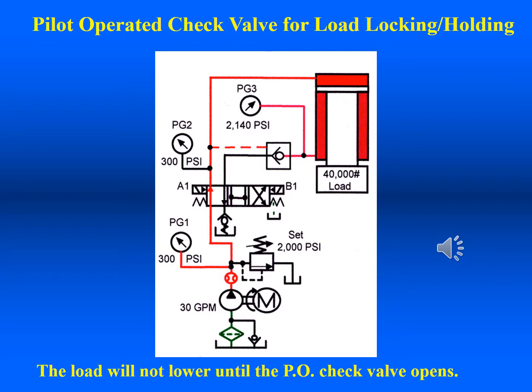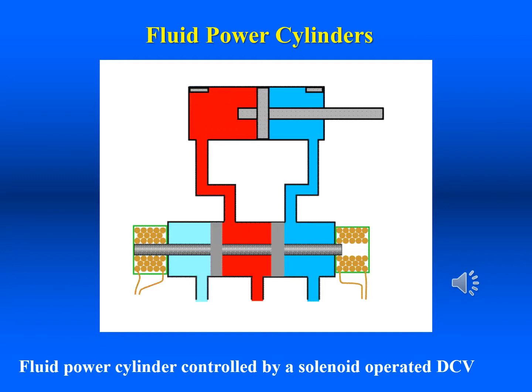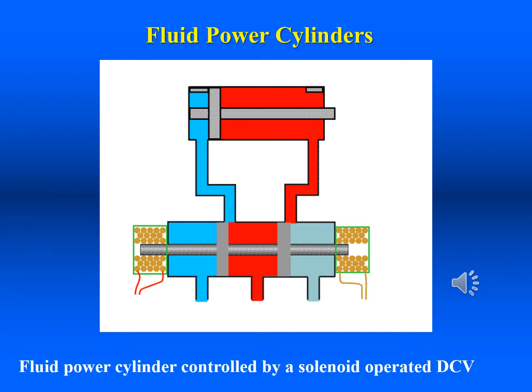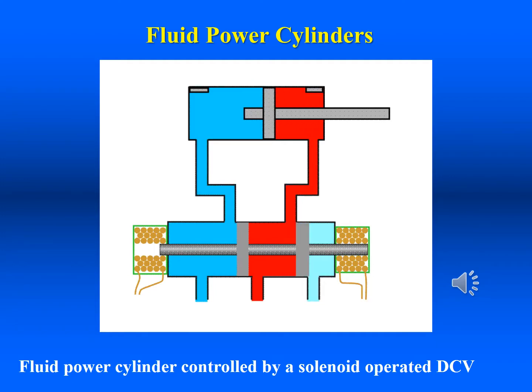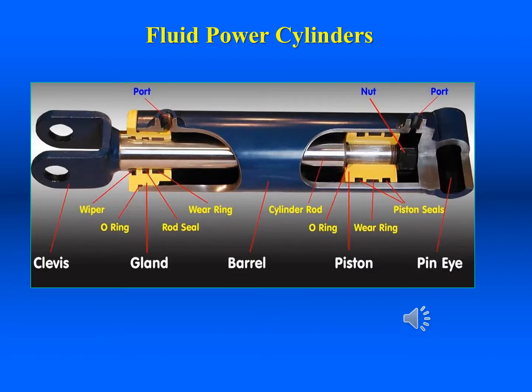Fluid power cylinders are normally controlled by directional control valves. Most directional control valves used in industry are actuated by an electrical device called a solenoid. Electrical energy is sent to the solenoid, which produces a linear mechanical force. This linear force causes the spool in the DCV to move. This picture represents a typical double-acting or differential cylinder. A double-acting cylinder extends and retracts with pressurized fluid. The term differential comes from the fact that there is a difference of area from one side of the piston to the next.